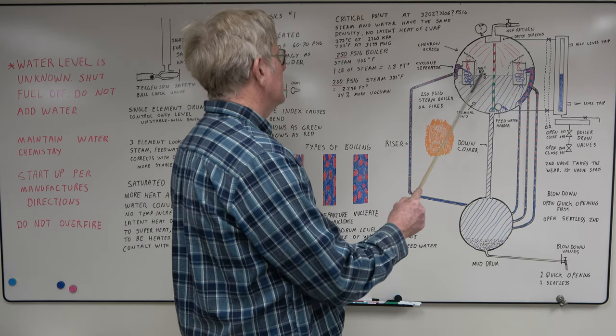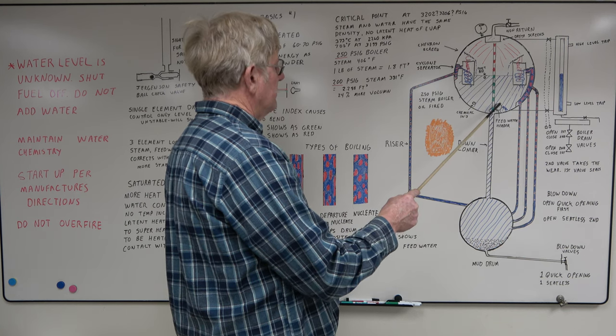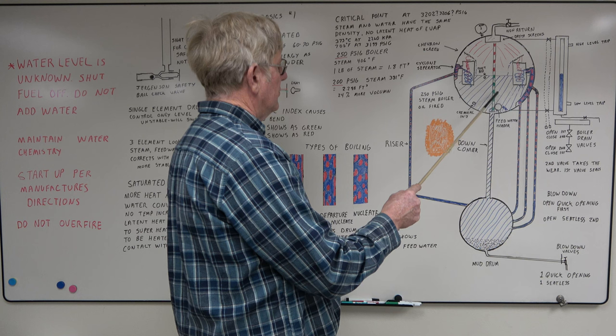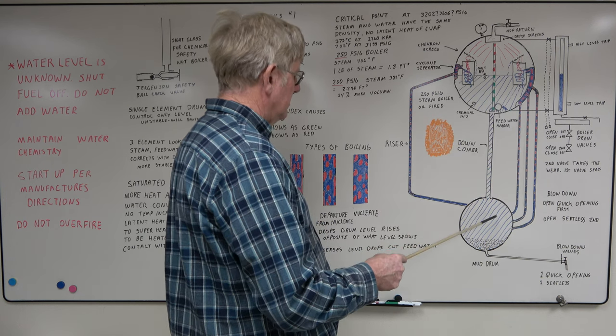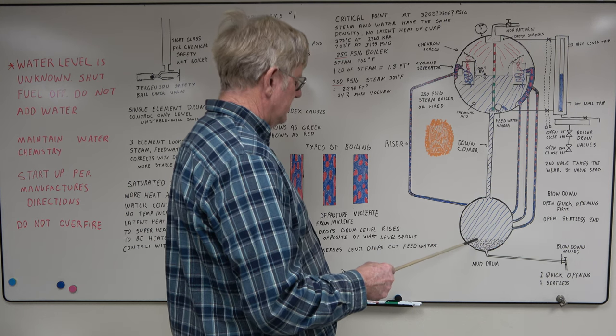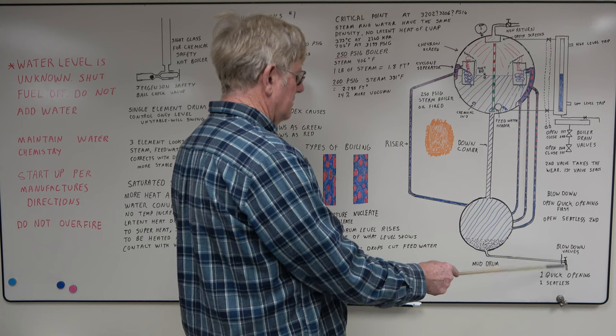Basically, your steam drum contains a supply of water. You add your feed water as it is colder than the water in the drum usually. It'll help increase the density of the water. It drops down the mud drum. It's called the mud drum because in the old days you used to get a lot of particulate sludge built up down here. We have our blow-down valves.